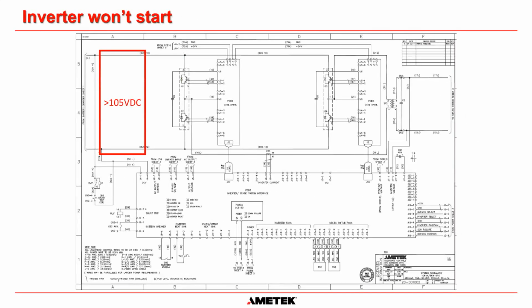Once again, if the inverter won't start, we have to check that we have 105 volts going into the system, okay? If we don't have 105 volts, it doesn't matter if you switch the inverter on or off. The inverter is not going to start. The software says the voltage must be above 105 volts DC. It measures it at this point here on the control board. If that is not greater than 105 volts DC, this inverter will never start no matter what you do.